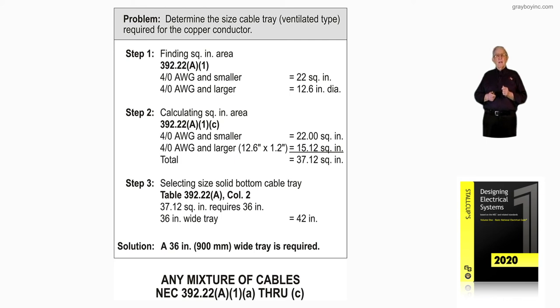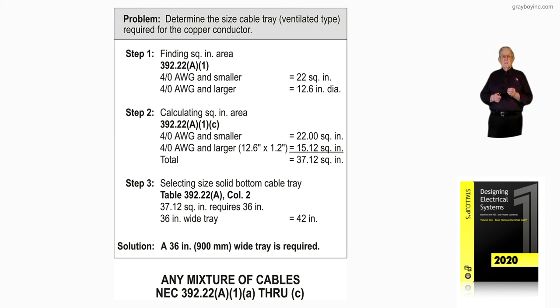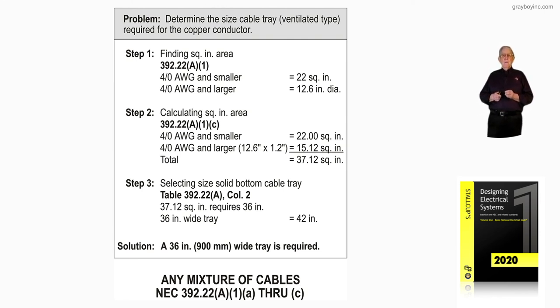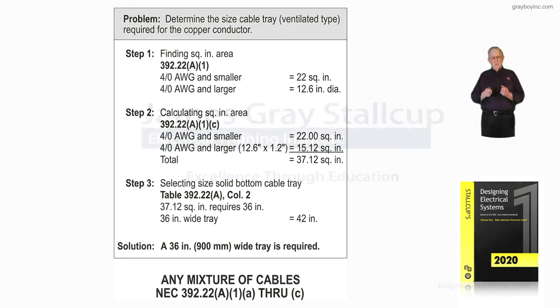Step three: we utilize column two for ventilated cable tray, Table 392.22A. The 37.12 square inch area requires a 36 inch width tray that would house 42 square inches. The 42 square inches for the 36 inch width tray is greater than 37.12, so the 36 inch wide tray would house the required area. The solution selects such a tray, as this illustration shows.